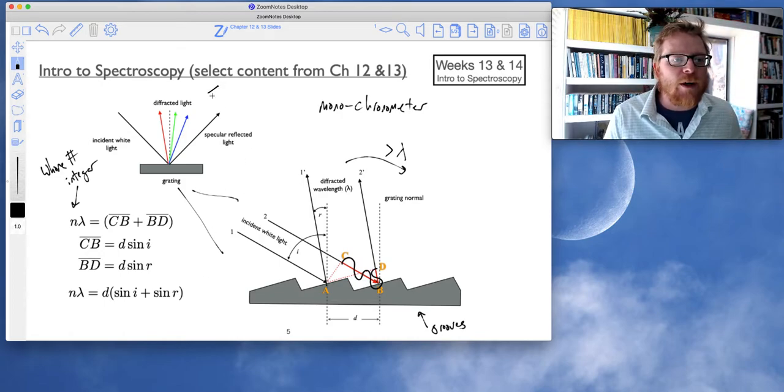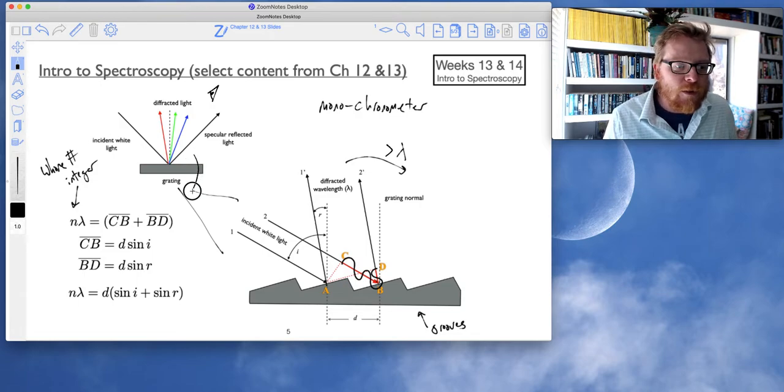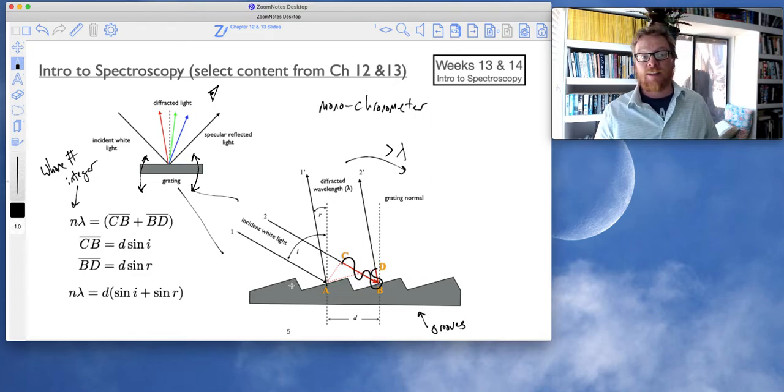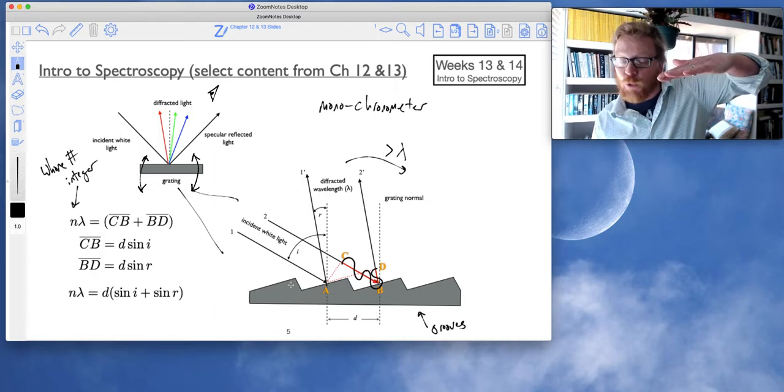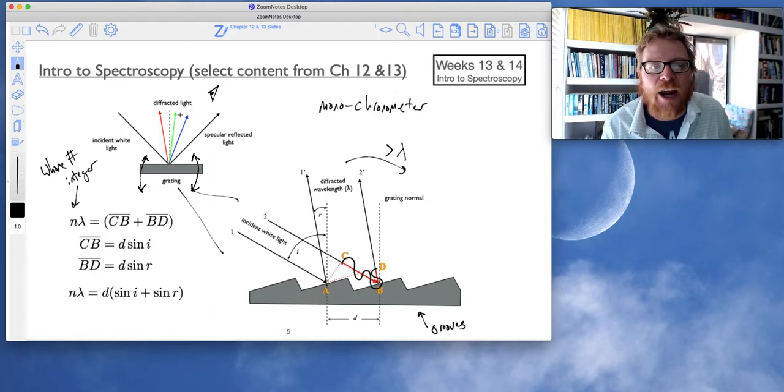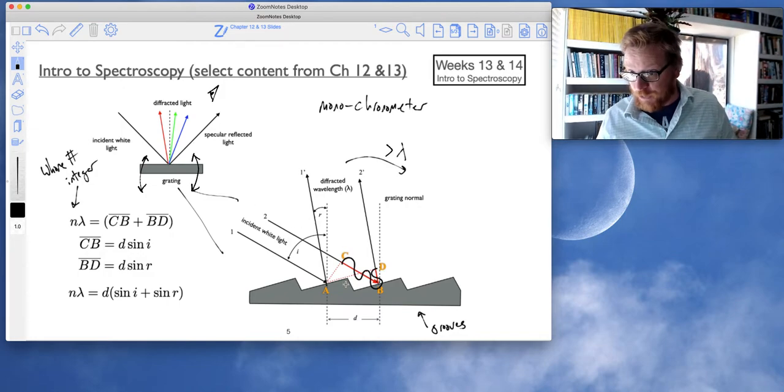And so, typically, the way that this works now, if I draw my detector up here, I don't want to detect the specularly reflected light, I want to detect the different colors. This grating will pitch and roll to give us those angles that we want. So, that grating will actually move, so it moves the desired wavelength into the path of the detector.